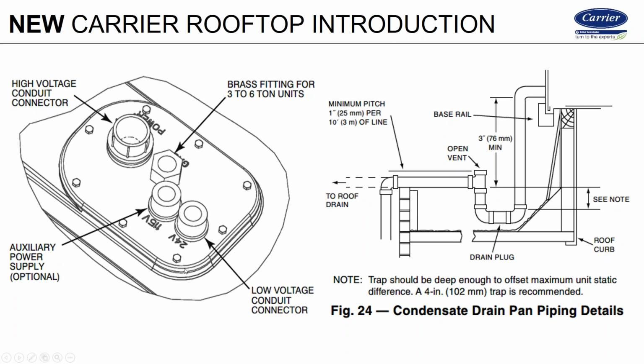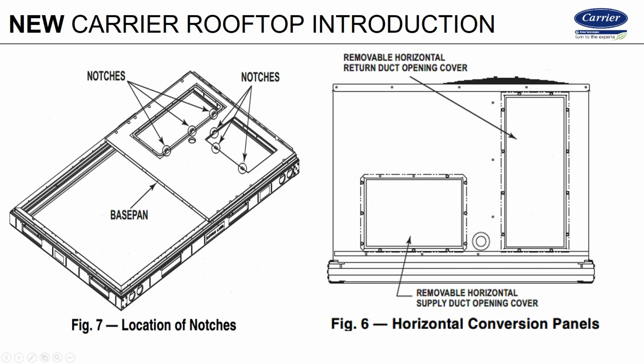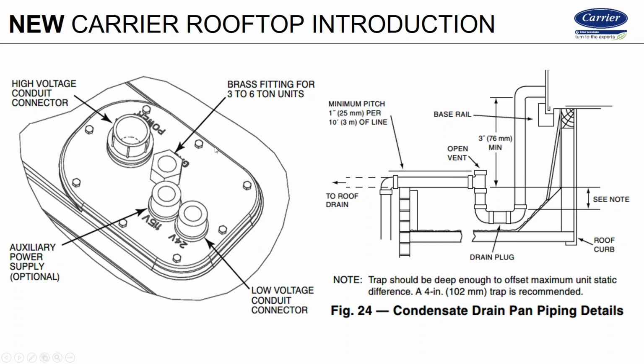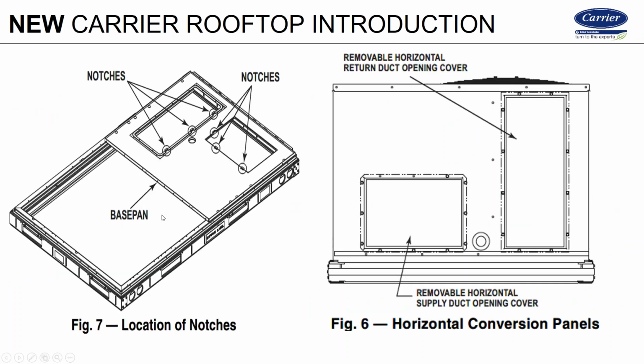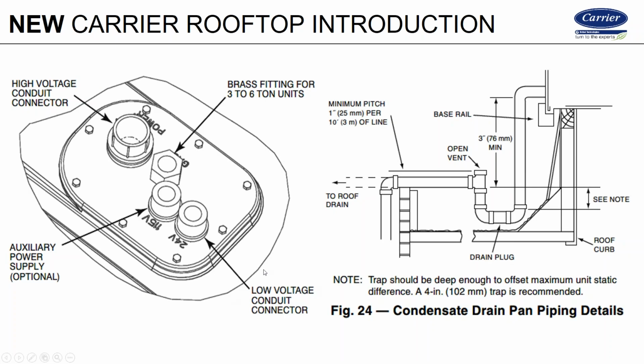We still have the through-the-curb access for control, for auxiliary power, for gas, and your line voltage, meaning that we can come up right through the curb. This is your air side again. This is the condenser side. So this little raised area right here is going to be located right here on the base pan. As you put this thing together, you have your curb, you put the base pans down, and you'll have that access point here. Always make sure if you're coming through the curb, you come through the designated area. Otherwise, you can get into water problems.